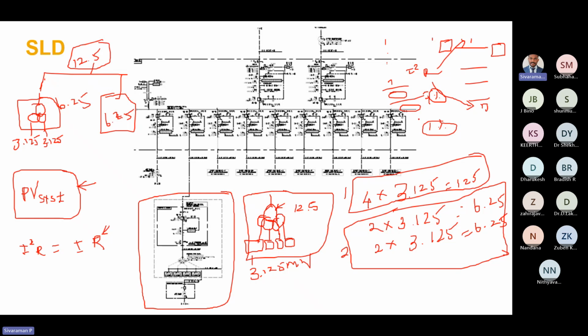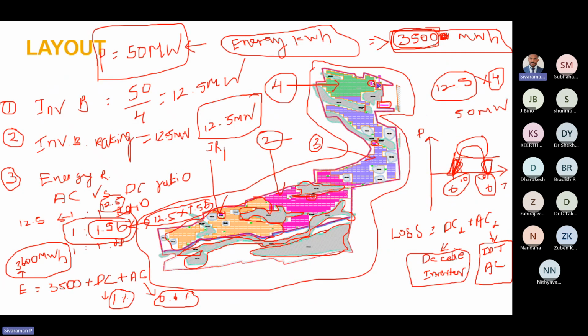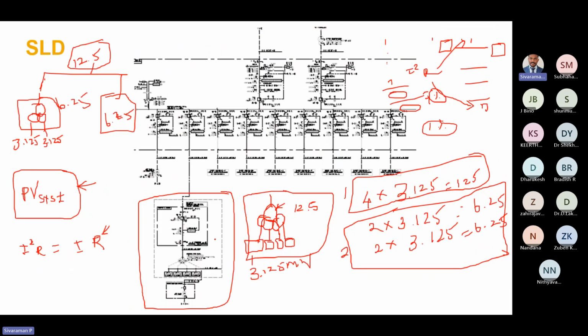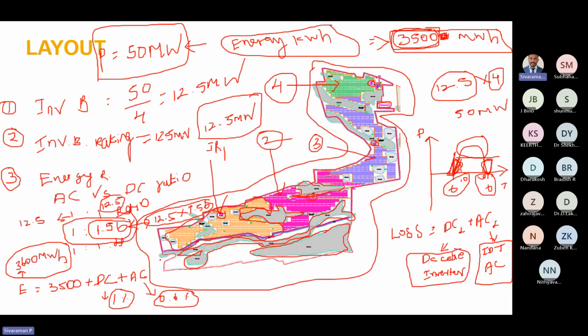If it is exceeding 1 percent, then we have to do some alterations in the layout, like moving the inverter room to the center, or reducing the DC cable length, or increasing the size of the DC cable. So we have to do some optimizations to reduce the losses for the AC cable as well as the DC cable. Okay, so everyone is clear as of now.